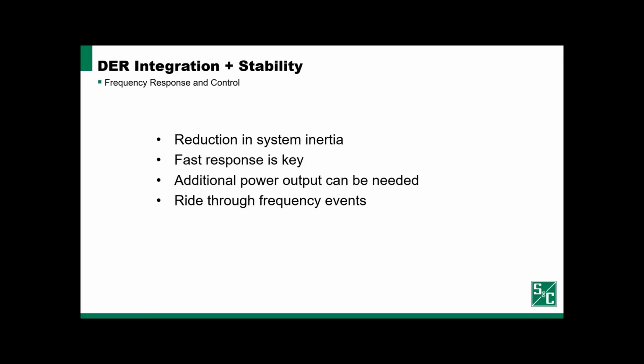If you take it at a very small scale, think again of switching the light switch on and off. A generator needs to ramp up or down to change power output for the load change that we're making. If we have a large rotating mass with a rotating generator, we can take some power out of that inertial mass by reducing the frequency and getting some power out to supply that instantaneously increased load. Or vice versa. We can speed up the rotating mass in the short term to account for a decrease in load that we're oversupplying.